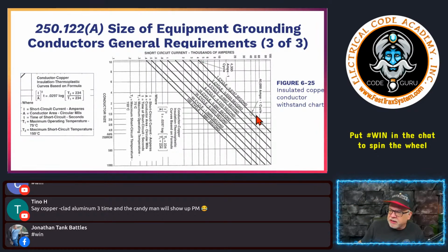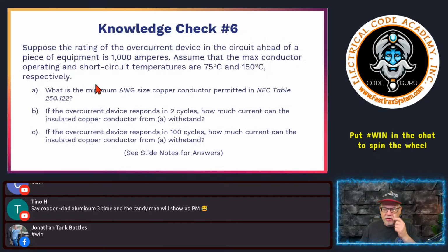If you have a one cycle clearance of 0.0167, then right here, this would be a 1-aught, which has a clearing of 40,000 amperes at one cycle right here. So that just happens to be right there, that 1-aught right there, okay, can handle 40,000 amperes for one cycle, okay? So that's what your clearing time is on your overcurrent device, and you're going to protect that conductor. And as you see, as you get smaller and you come over, depending on the short circuit current level you're dealing with, you will see all different. So anyway, you shouldn't be messing with this table. This should be something you don't even mess with, okay? Let your engineer do that.